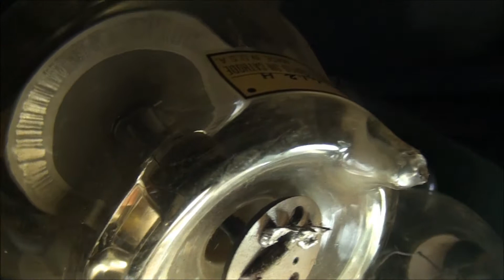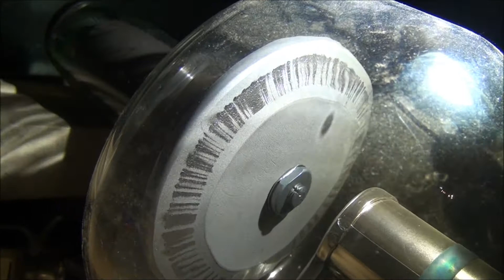Hang on, if I put that there, it's probably going to, it doesn't blow up because, yeah, that one's still pressurised. You can see the anode target in this one. It's on a bearing, so it spins during operation. But you can see the scars on the anode. That's from probably very heavy exposures that have been taken, and also possibly I think the tube is failing due to a problem with the anode rotation circuit, so the tube wasn't spinning fast enough.